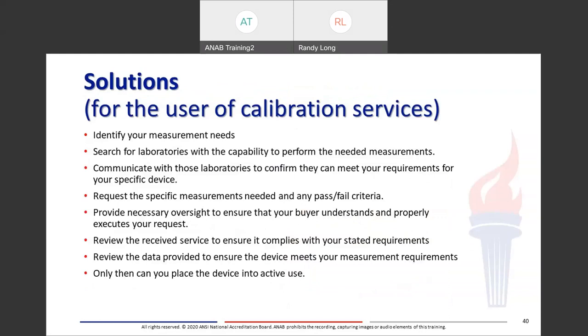Some solutions for the users of calibration services: it's best to identify your measurement needs, search for laboratories with the capability to perform the needed measurements, and communicate with those laboratories to confirm they can meet your requirements for your specific device. Request the specific measurements needed and any pass/fail criteria. Provide necessary oversight to ensure your buyer understands and properly executes your request. Once done, review the received service to ensure it complies with your stated requirements, then review the data provided to ensure the device meets your measurement requirements. Only then can you place that device into active use.